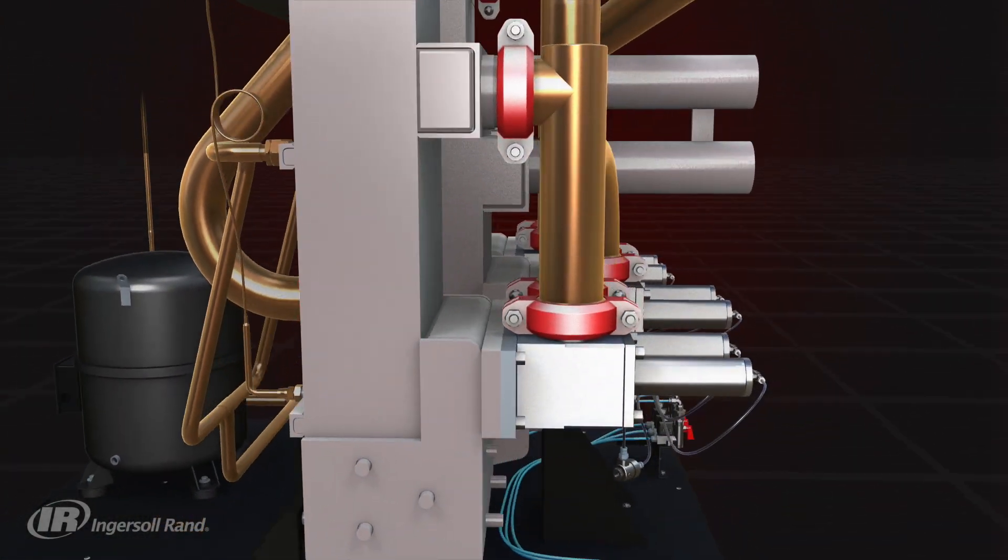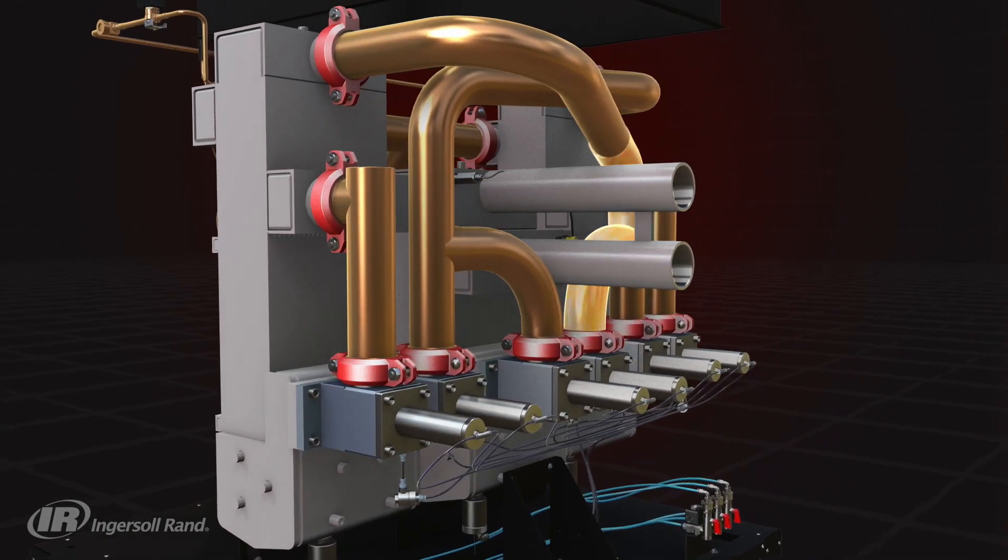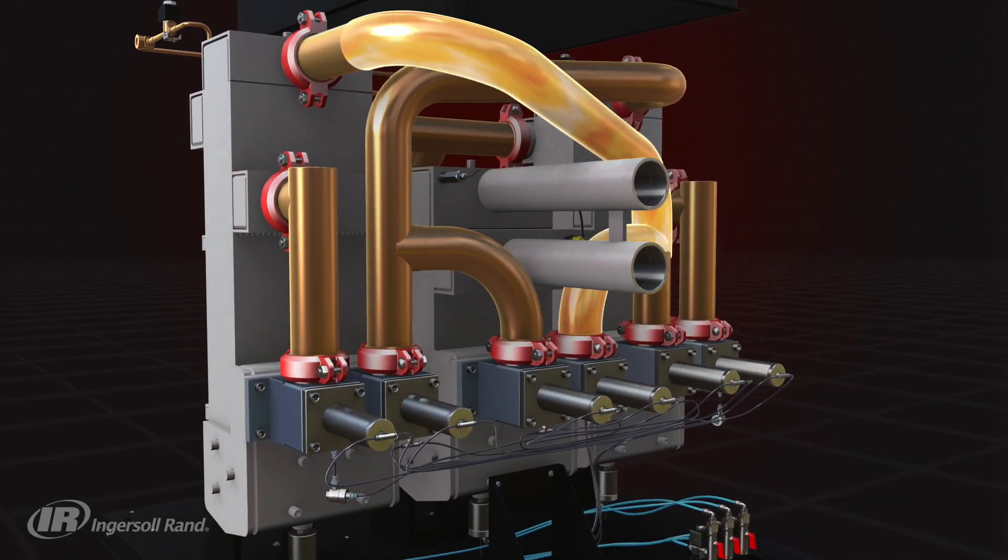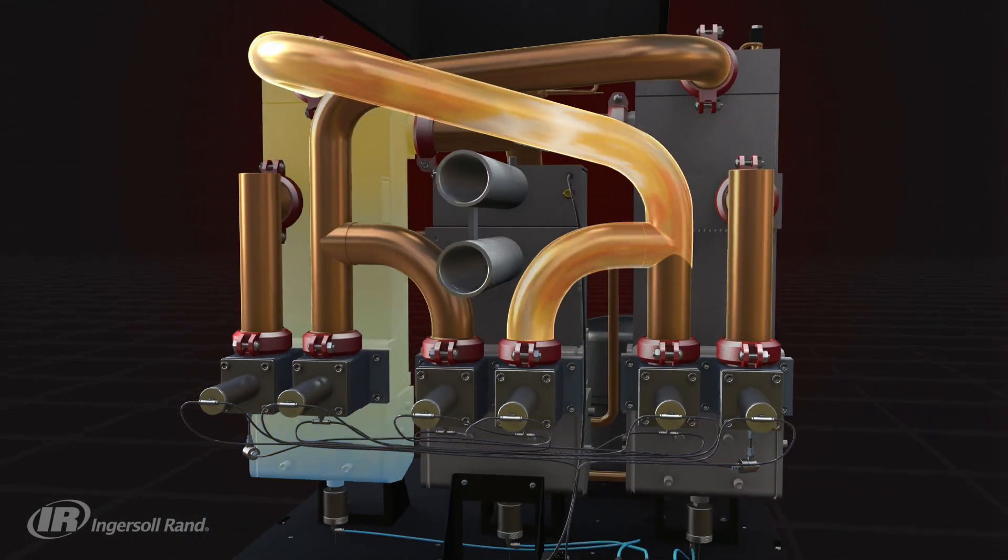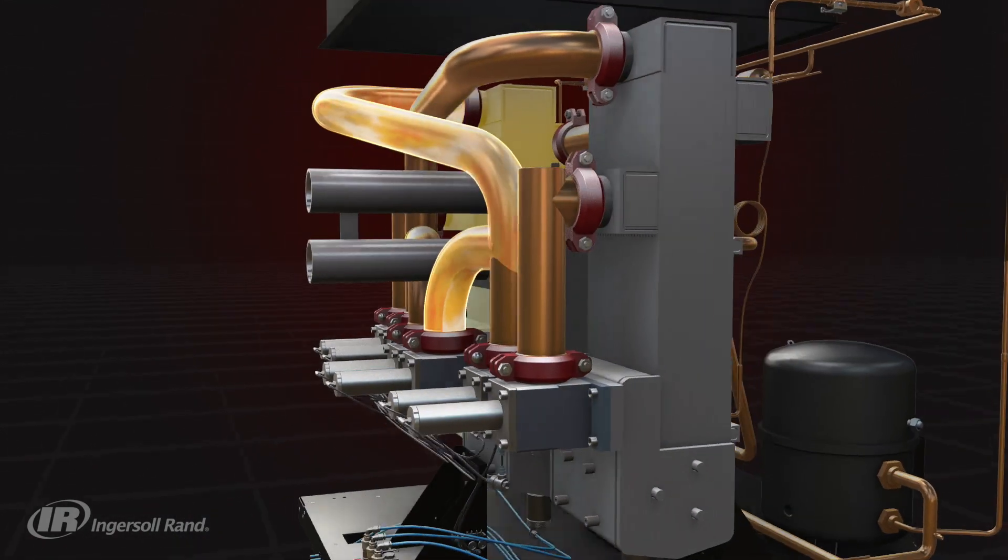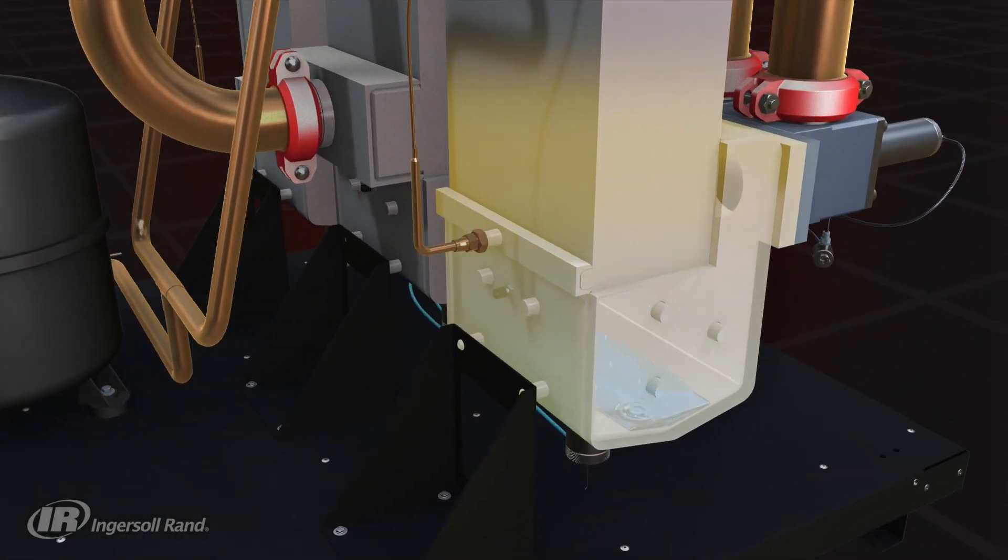Still warm, the partly dried air passes through and essentially defrosts the regenerating unit, eliminating the need for any additional heating systems. As the frozen condensate melts, it drops to a reservoir at the base of this unit and is drained away.